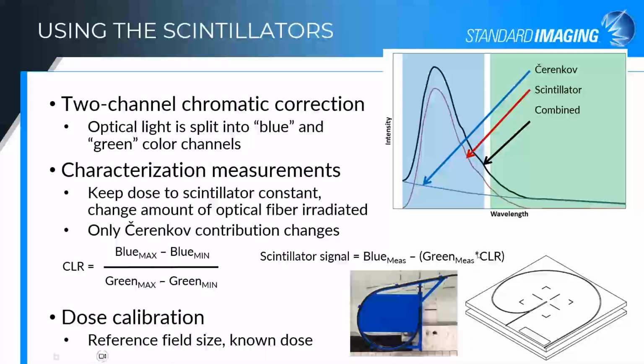This is built into our Supermax electrometer for use with the W1 scintillator. The W1 is just the scintillator and the optical system for collecting that light, so it does require the 2-channel electrometer in order to gather the blue channel signal and green channel signal separately. The W2 has a dedicated electrometer, which has both the optical signal collection portion as well as the signal processing electronics to do the 2-channel measurement and the Cherenkov correction automatically.